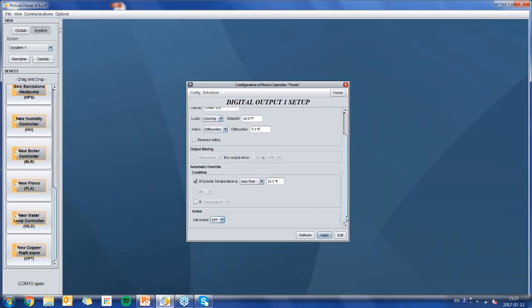We could also add a condition based on occupancy. I could force my chiller to off, or essentially disable it, if the schedule becomes unoccupied. And we also have an OR function right here as well.